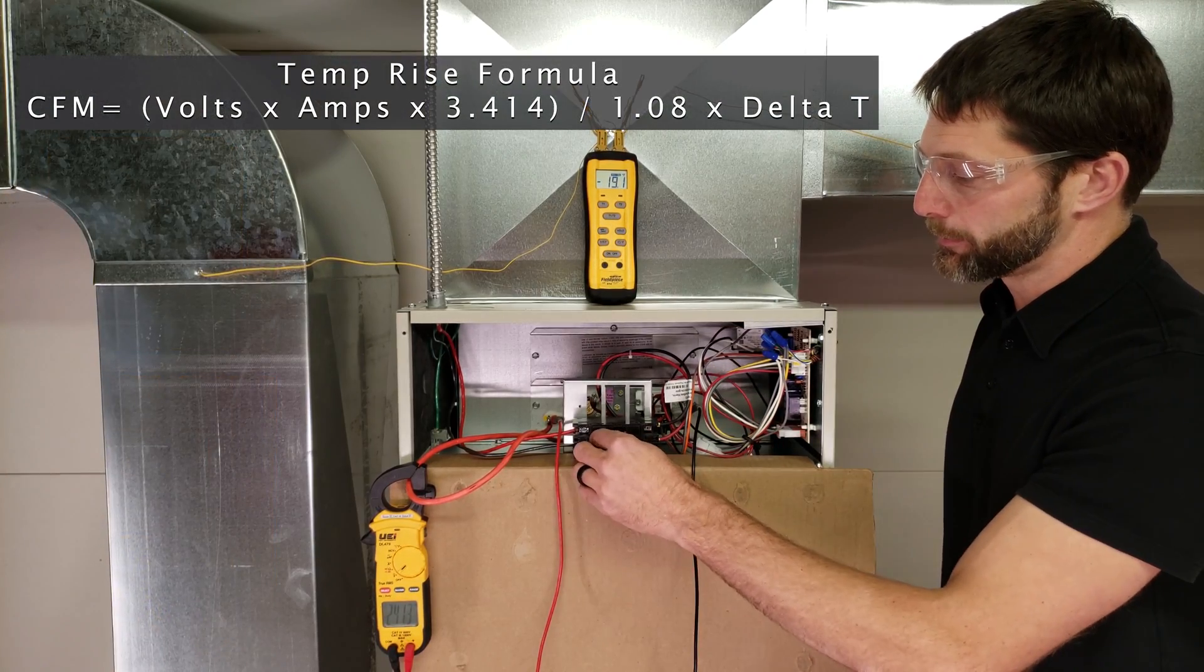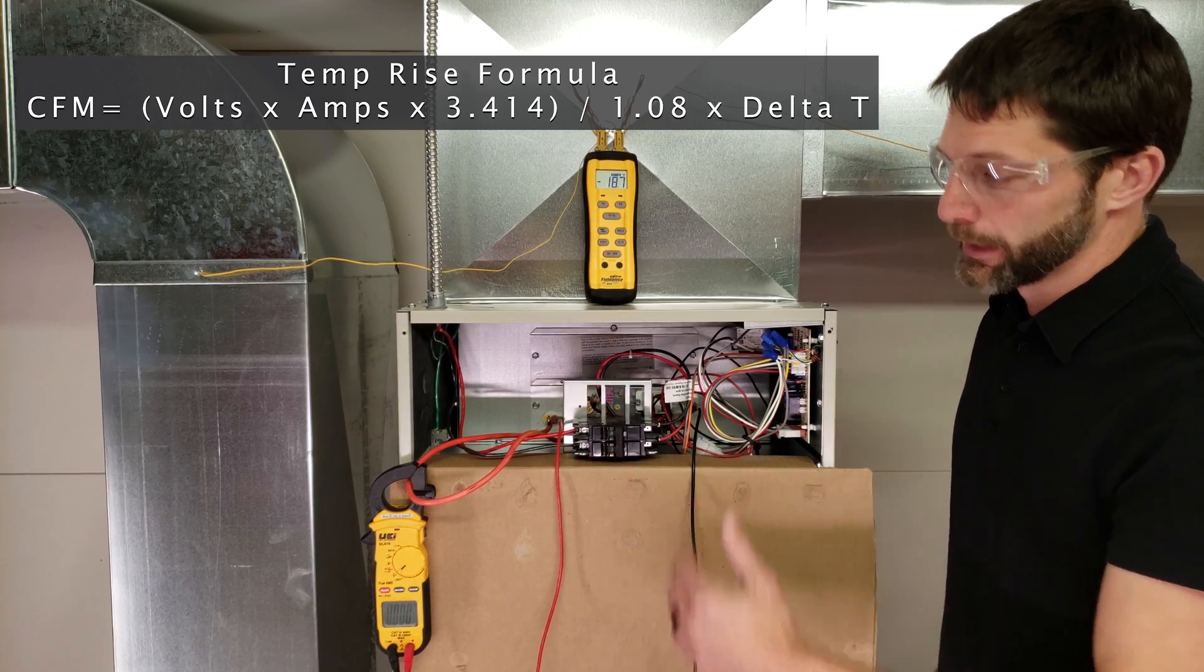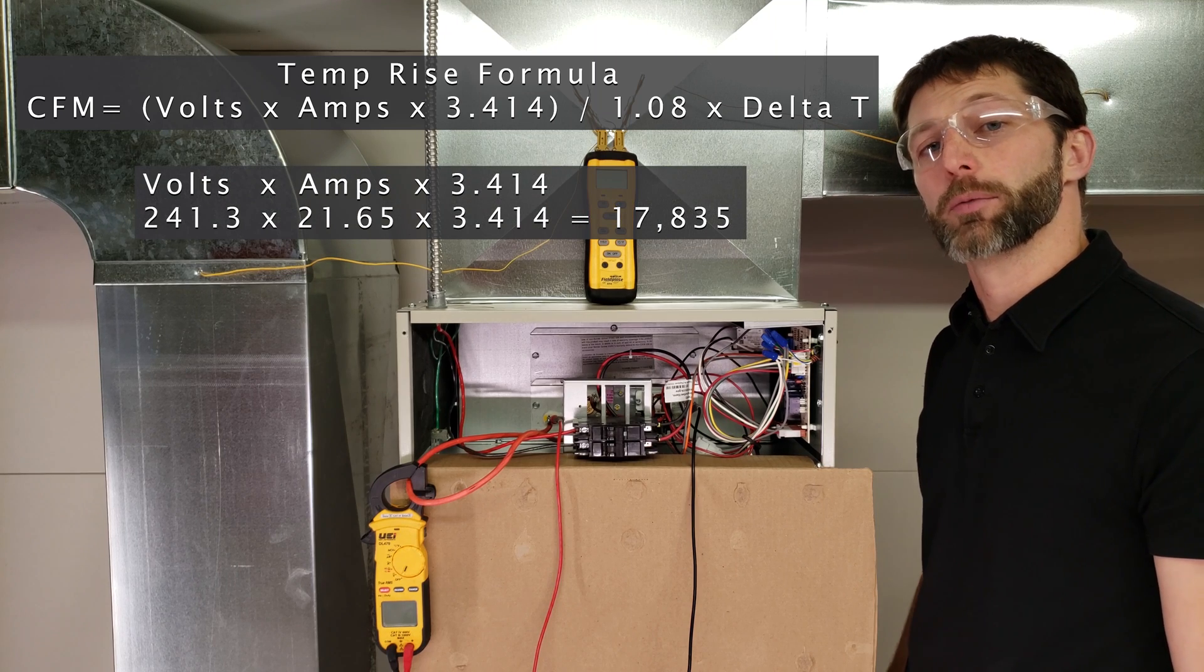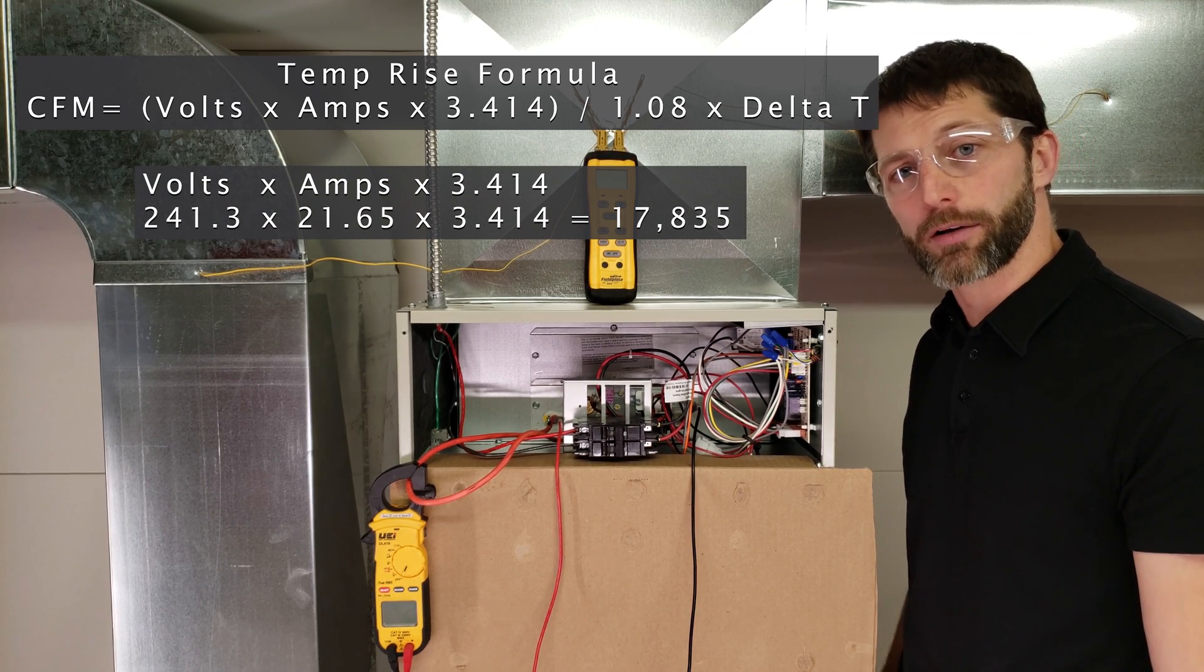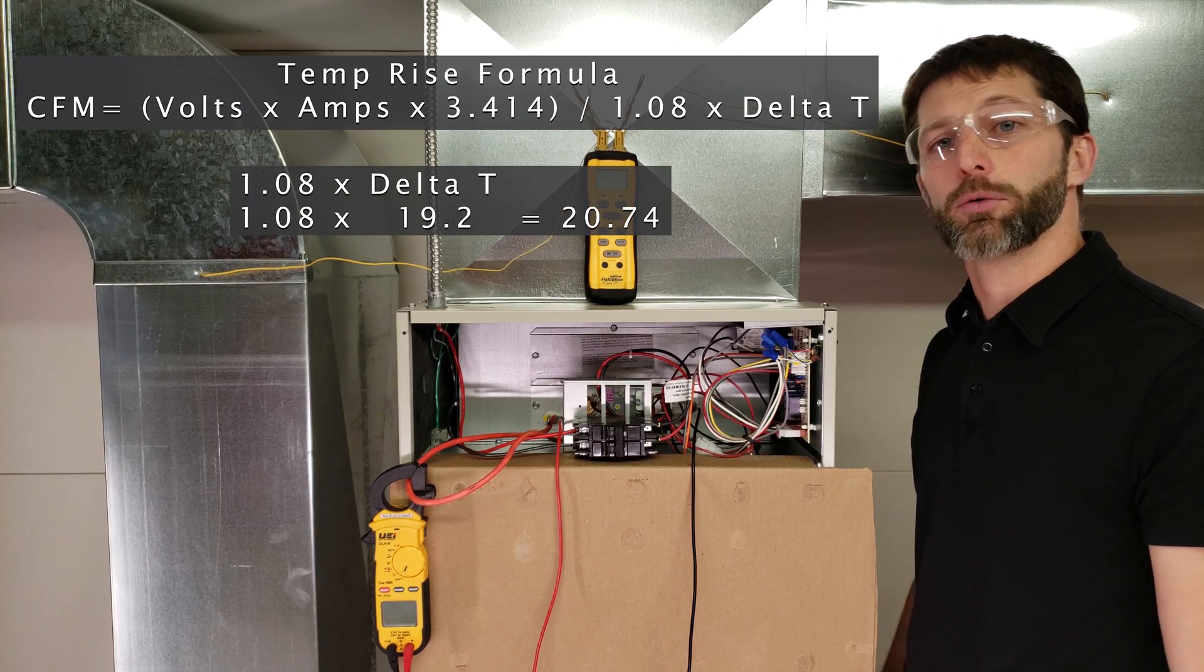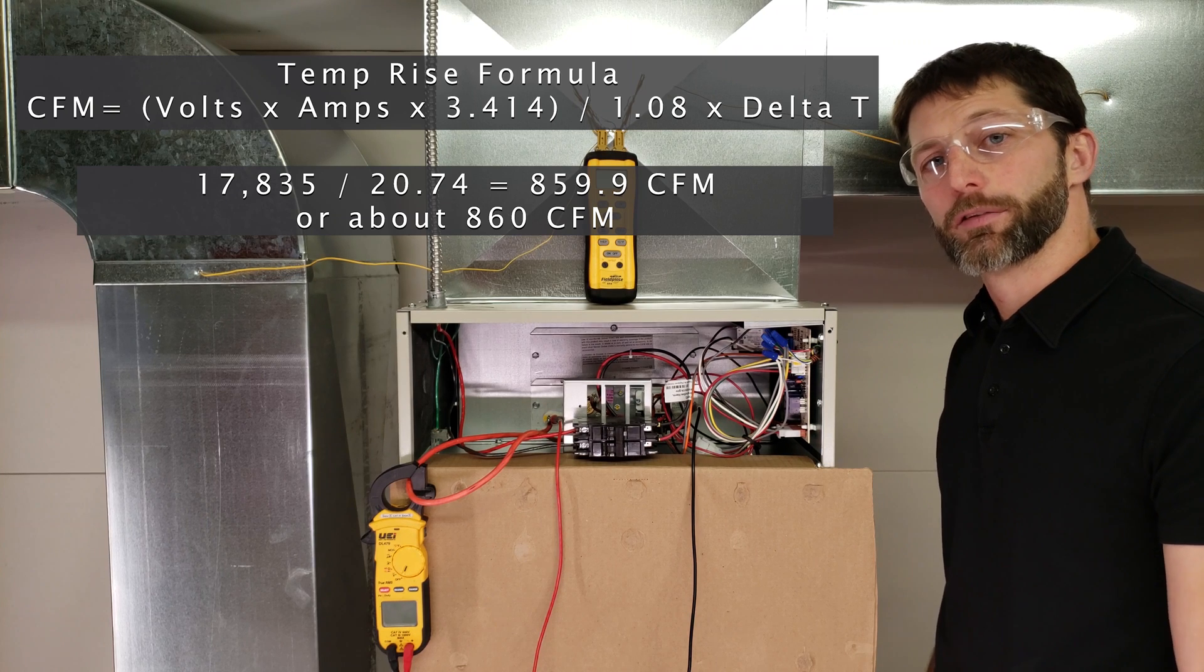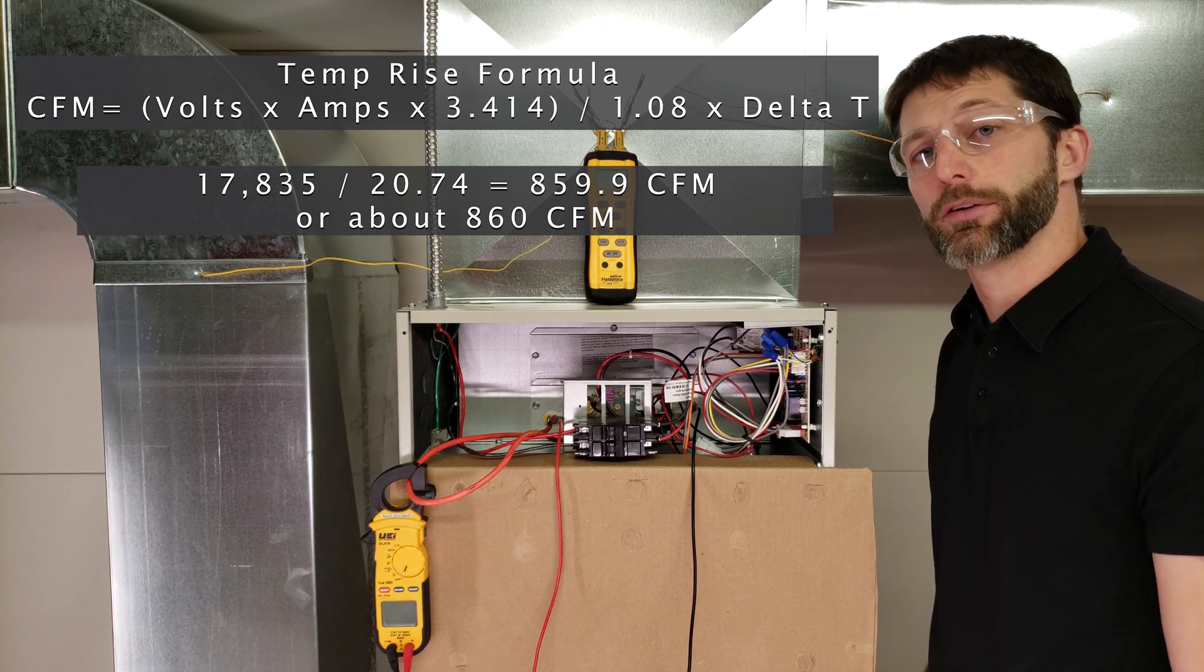I'm going to go ahead and turn this off now. You can turn it off at the thermostat, or since we're right here, I'm just going to turn it off at the breaker. So our volts times amps times 3.414 equals 17,835. Then we have 1.08 times the delta T, and that equals 20.74. So we have 17,835 divided by 20.74, and we're left at 860 CFMs.